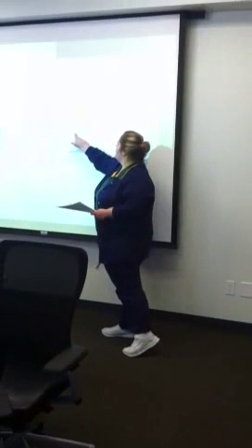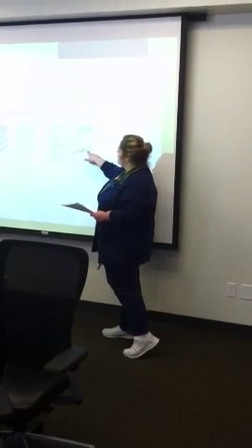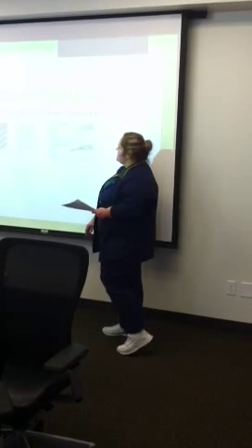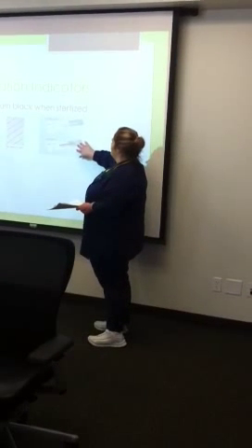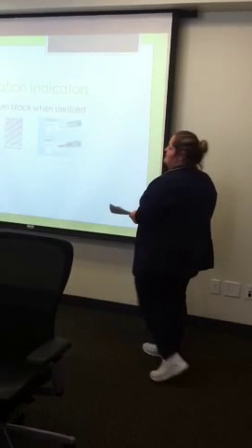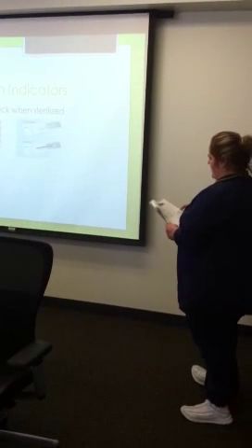These are our indicators, so this is what I was talking about. So when it goes in, it's kind of gray. When it comes out, it should be black all the way through. Again, with the sterilization tape, but don't go by the sterilization tape. Make sure that when you open it up that you're always checking the 3M. This is one that's really going to tell you whether or not it was sterilized on the inside.